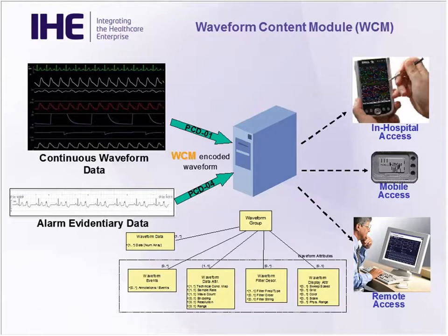If you look at the mobile medical device guidelines from the FDA, essentially if you're taking the evidentiary data and converting that into a displayable waveform, you probably should evaluate whether it should be a Class 2 device or not. If you're just displaying an already generated static snippet, you're probably a Class 1 device and don't have to go through the same level of scrutiny and management and recording.